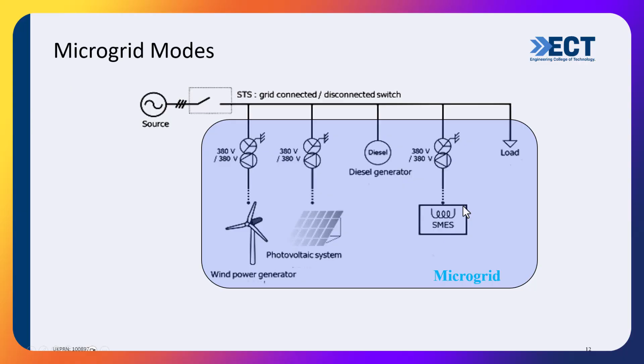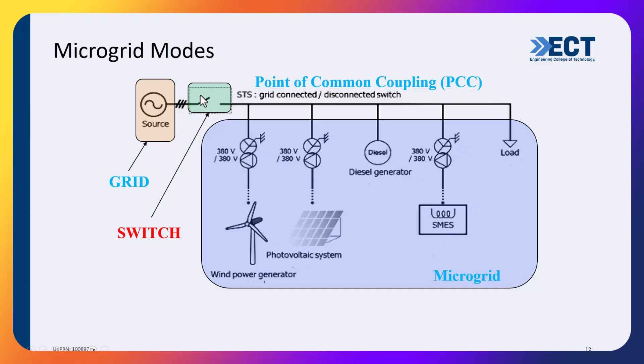There's a choice to connect that microgrid to the grid, or disconnect from it, using the switch between the grid source and the microgrid. So we have two modes: when the grid is connected to the microgrid, we call it grid-connected mode, and if we open that switch, we're isolated, which we call island mode.